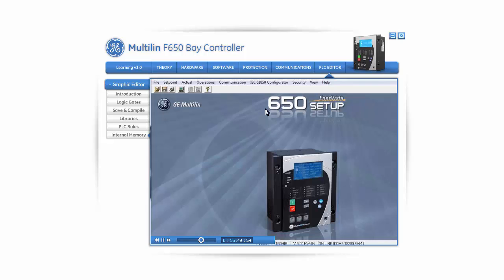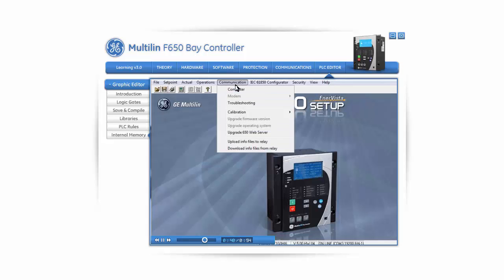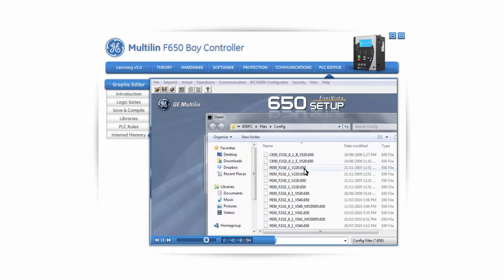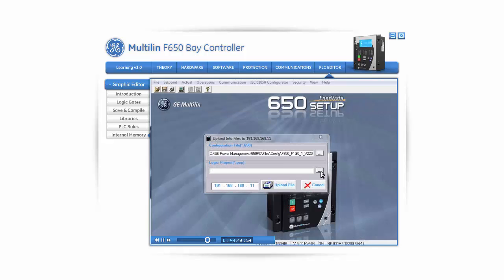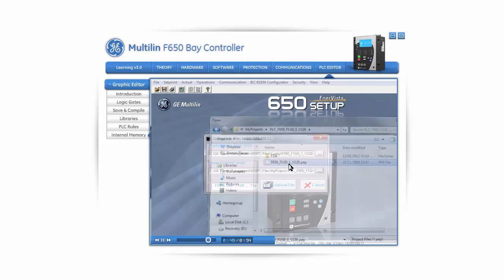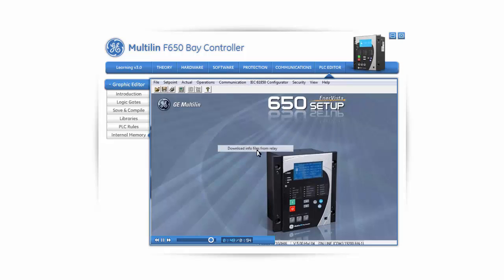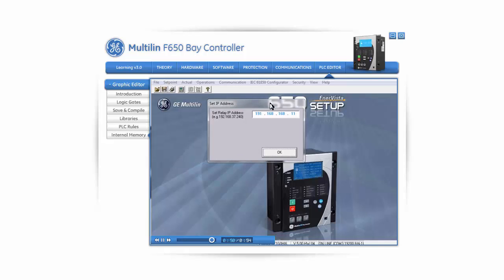Now we will learn how to use the storage memory in the F650. In order to upload the configuration files and logic project into the relay, open the EnerVista F650 setup software and navigate to Communications, Upload Info Files to Relay. Click on the Browse button to browse for the files on your PC hard disk. Note that access to the storage memory of the F650 is only possible via an IP address. After choosing the files to upload, click on Upload File. In order to download the files from the F650 storage memory, go to Communications, Download Info Files from Relay. The EnerVista 650 software will prompt the user to select where to save the files on the PC hard drive.